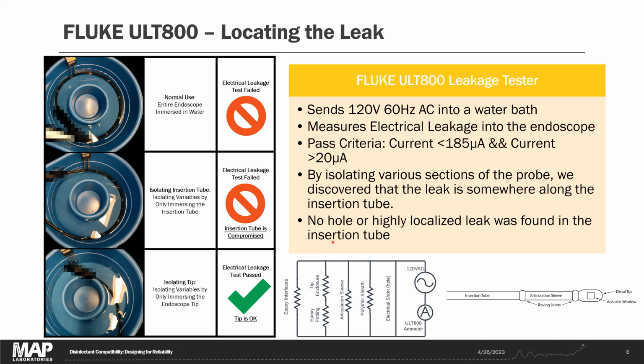One important thing to note here is that we couldn't find any localized leak in the sheath. We could immerse the bottom end of the sheath and cause a failure, or the top end of the sheath and cause a failure, and we couldn't find any small localized region of electrical leakage. So this suggests that there's a systemic problem with that insertion tube.